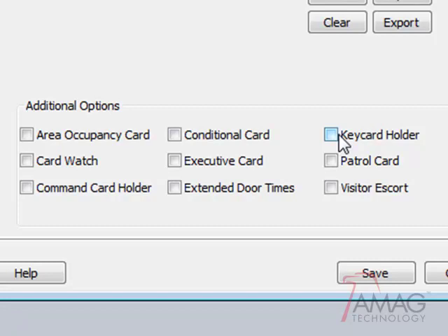Keycard mode can be useful if, for example, the door is the point of entry for switching an intrusion alarm off, and only a few people know how to switch the alarm. This would keep the normal staff from accessing the door and causing a false alarm. The special sequence for entering the PIN, for example, if the normal PIN is 1234, the PIN entry would be 3412, the last two digits of the PIN entered first.